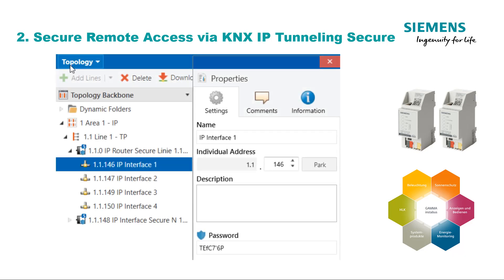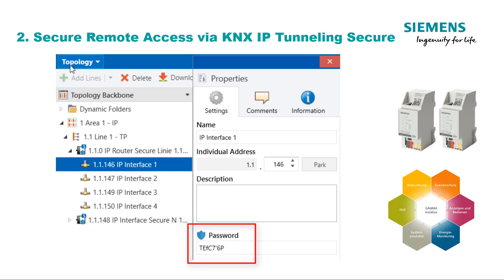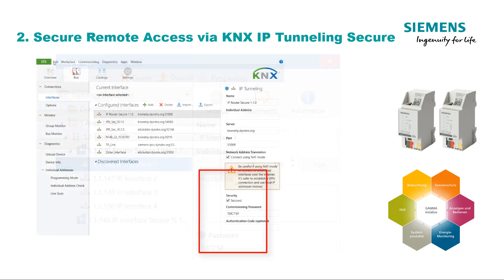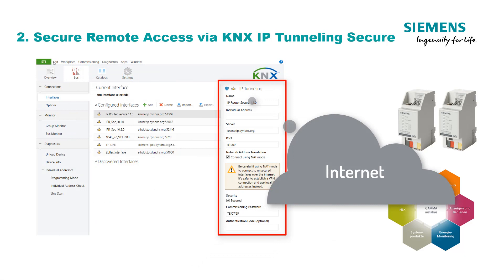Secure Remote Access via KNX IP Tunneling Secure. The IP Router Secure N14603 and the IP Interface Secure N14823 have four parallel secured tunnel connections. These allow secure access to KNX systems with ETS for maintenance and diagnostic purposes, and other software products such as visualizations. The first time an IP tunnel interface is used, the configured password of that IP tunnel interface is queried. Secure access can take place not only in the local network but also via the Internet.